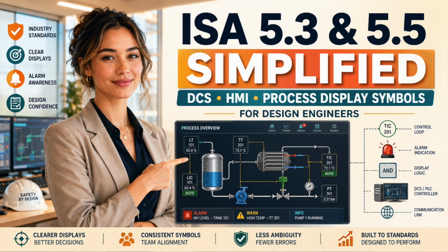When every vendor, package supplier, engineer, and project contractor introduces a different visual language, the control room becomes an interpretation problem. One screen uses green for running, another uses green for available, another uses it for healthy communication, and another uses it for an open valve. Red may mean stopped, closed, tripped, emergency, or simply selected. A filled valve may mean open in one unit and closed in another. A dashed line may indicate software communication, an electrical signal, or an unavailable connection depending on who drew the graphic. That is not flexibility. It is unmanaged ambiguity.